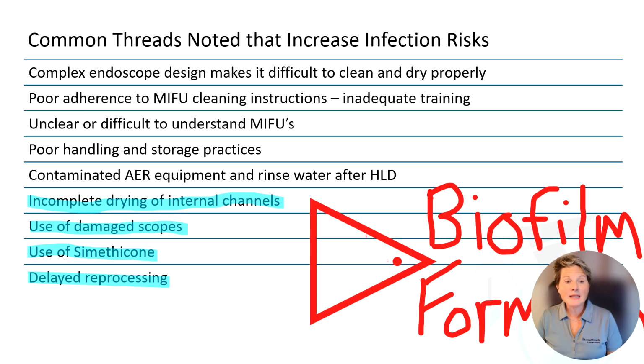And then contaminated AER equipment and rinse water after high-level disinfection. There have been several studies that have pointed to the AER equipment and lumens within that machine having biofilms on it. And of course, that's going to just pass it right along to the endoscope, or contaminated rinse water. So these are things that a lot of people don't think about, but that have been shown to be problems in some places. And then incomplete drying of internal channels, not fully drying them until they are bone dry. This is really important, because if you don't get them completely dry, the bioburden, or the bacteria that are in there, can multiply exponentially. And it happens very fast. You can have over 2 million colony forming units in less than an 8-hour day.